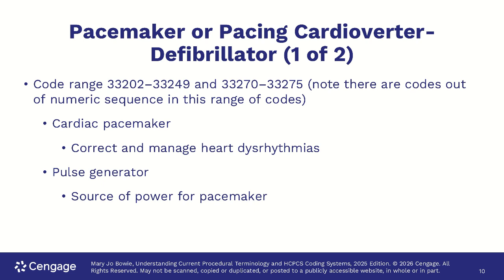The pacemaker is made up of a pulse generator, which contains a battery as its source of power. These batteries last about 6 to 10 years before they need to be replaced, so they don't last forever. The generator controls the heart rate, the energy output, and the pacing modes.